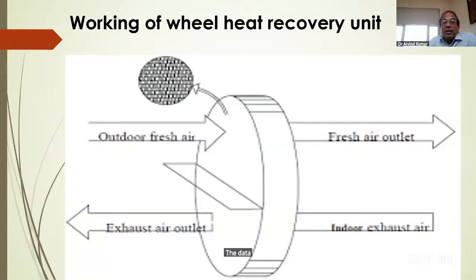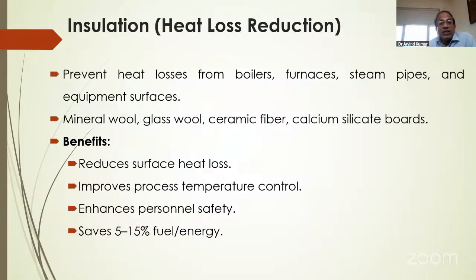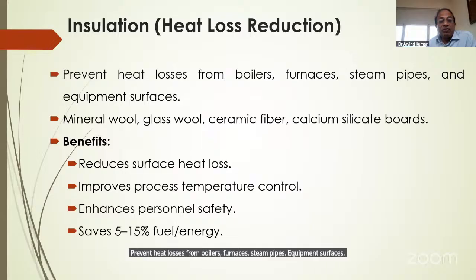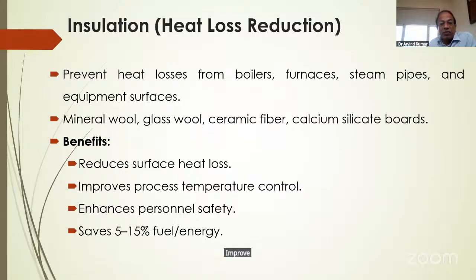That is the working of a wheel heat recovery unit. Using the recovery wheel, we can recover heat energy or minimize the cooling load in an HVAC system. Insulation also has a big role in reducing heat losses in industry, in furnaces and boilers. It prevents heat losses from boilers, furnaces, steam pipes, and equipment surfaces, using mineral wools, glass wools, ceramic fibers, and calcium silicate boards. It has many benefits: it reduces surface heat losses, improves process temperature control, enhances personal safety, and saves 5 to 15% fuel energy.